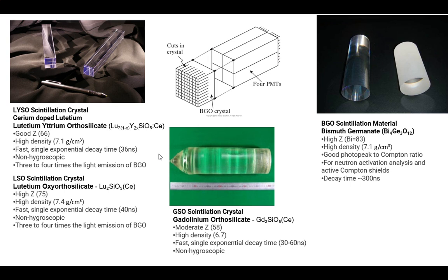So by a simple thing of cutting the crystal, I can drastically reduce crosstalk. Even when I go down to those photomultipliers, they'll still get something, but they won't be built on it. It'll be from a new, fresh area. So you'll get a distinct spike, and that spike will show up then on the photomultipliers. So that's kind of the trick to them.